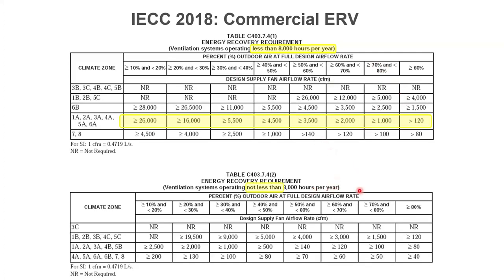If you're operating 24/7 or almost 24/7, 24/7 would be 8,760 hours. So if you're operating 8,000 hours a year or more, essentially 24/7, then pretty much every project you do would have to have an ERV unless it's less than 10% outside air. So if you're doing hospitals and stuff like that, you're probably thinking, got to go with an ERV. Maybe an all-night pharmacy might have to do it, right? There are a lot of thresholds on when this is going to kick in because of this table now.